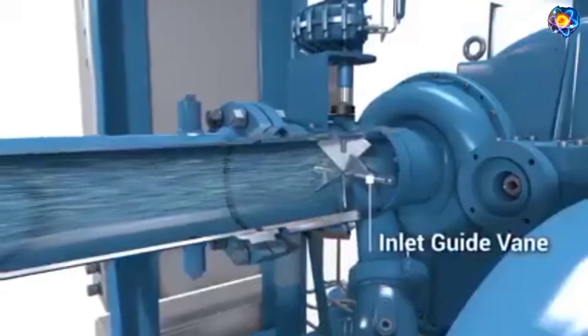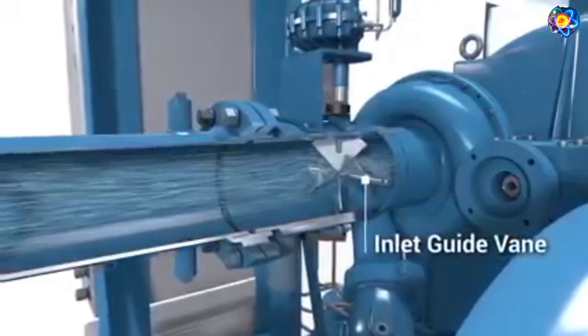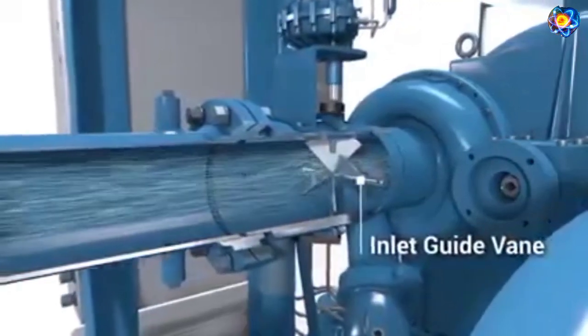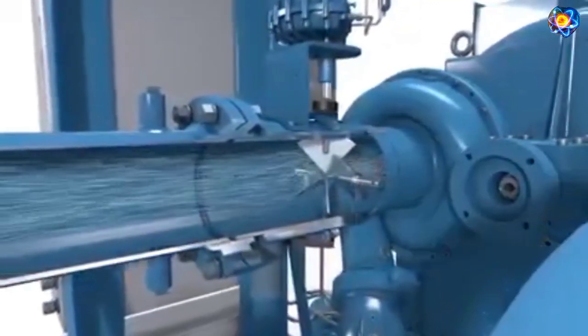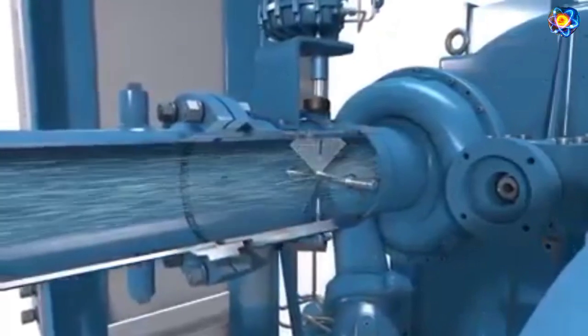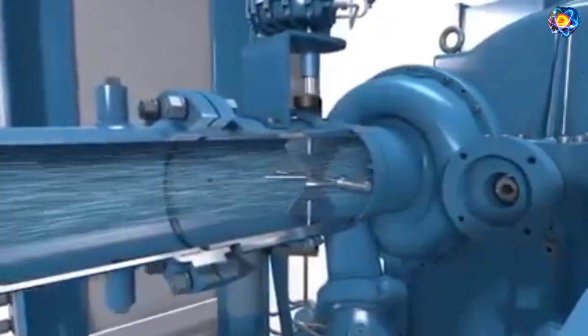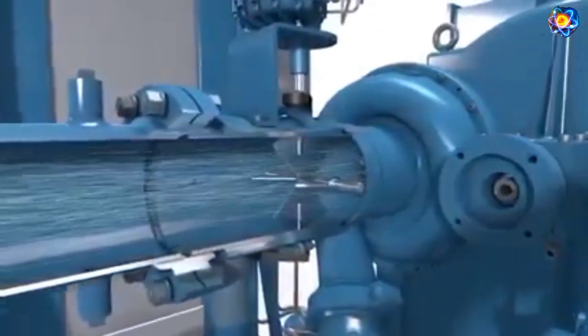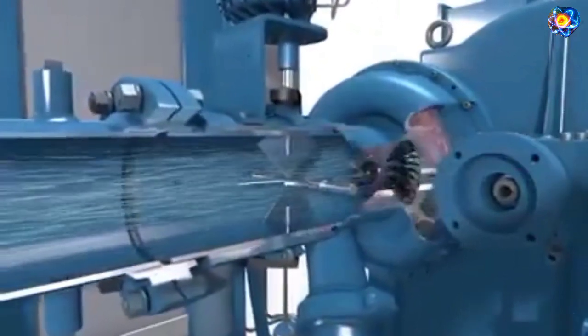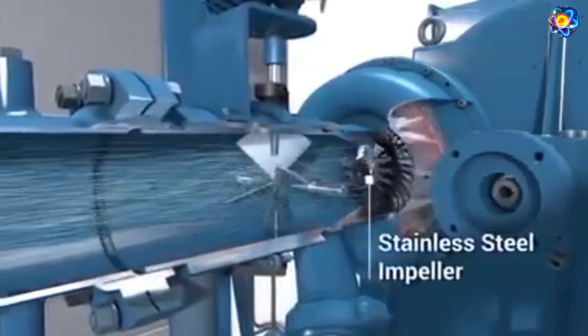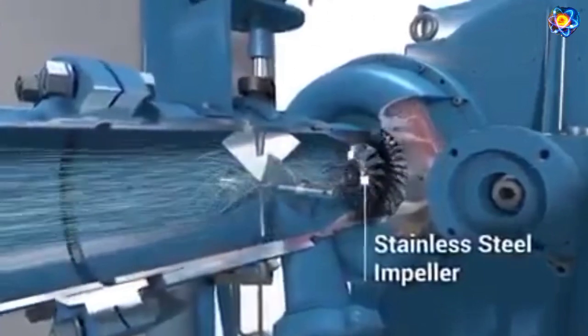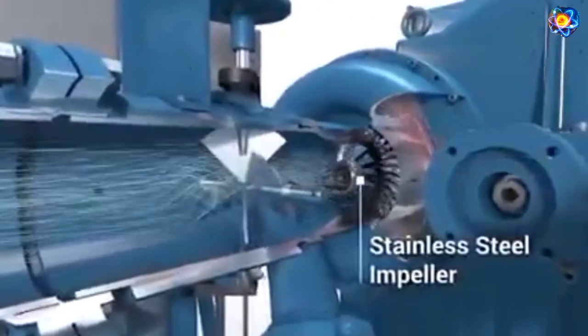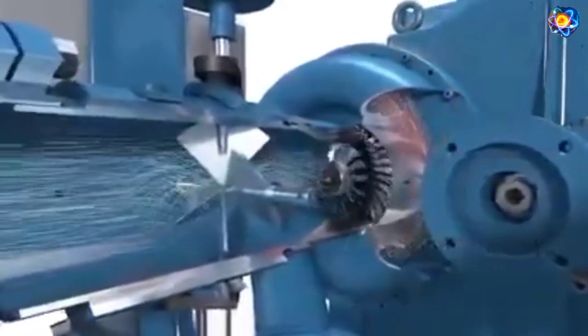From there, an inlet guide vane automatically adjusts itself to changes in system demand, regulating the incoming low-velocity air or gas stream as it flows toward the first stage impeller with a pre-swirl effect. As the low-velocity air or gas stream flows into the first stage stainless steel impeller at the inducer, centrifugal force directs its flow to the trailing edge.